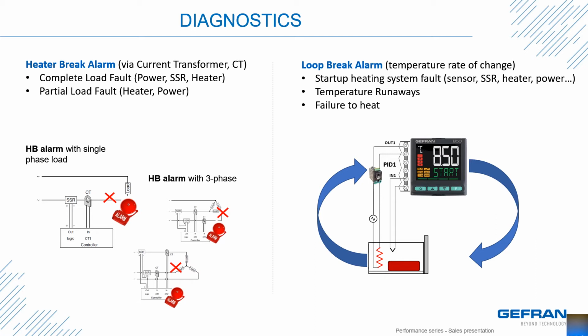We can also determine partial heater failure, such as a platen press that has 4 cartridge heaters. Say they each draw 5 amps for a total of 20 amps. When one goes out, we'll only see the current draw of 15 amps. We can use the alarm based on that, not having full current. This feature is useful as some band and cartridge heaters are made with internal invisible parallel circuits, so that a 5 amp cartridge heater may actually be 2.5 heater circuits, but not visible to you.